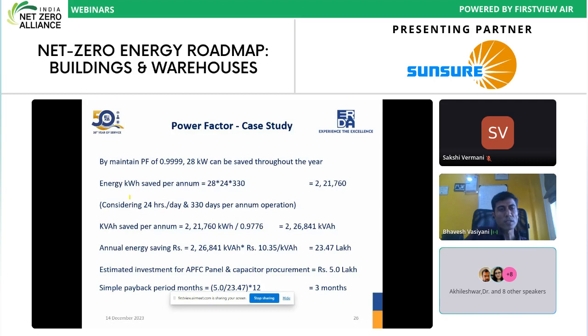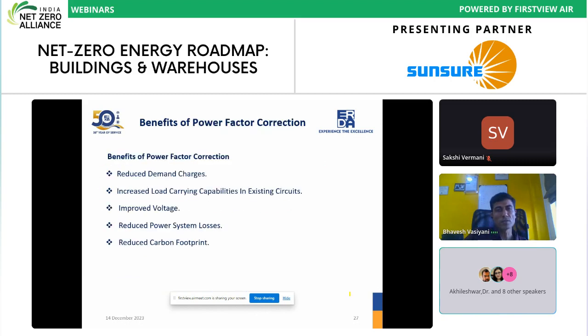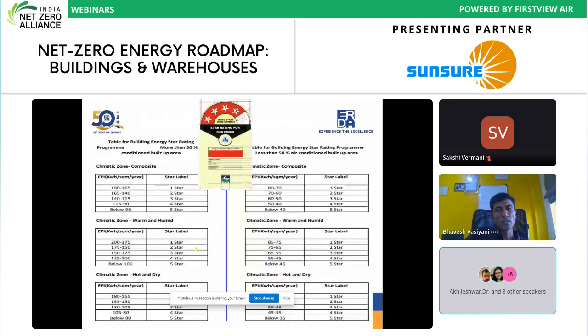This was it, ultimately KVAH was being charged, so a huge amount of saving was possible in that case. So always maintain the power quality and power factor also, so that you may not get any extra charge from your discom. So these are the advantages. Of course, reduced distribution losses, reduced demand charges, better voltage level, and fewer losses in the power system. Ultimately, the carbon footprint can be optimized.